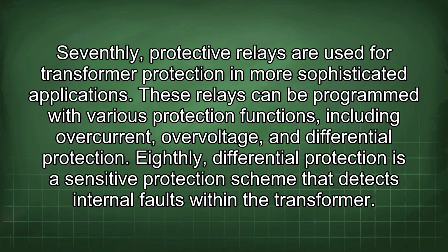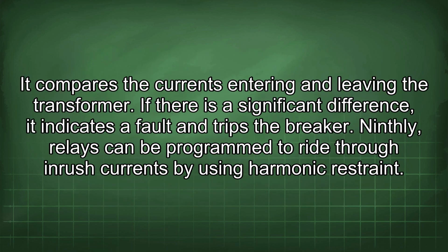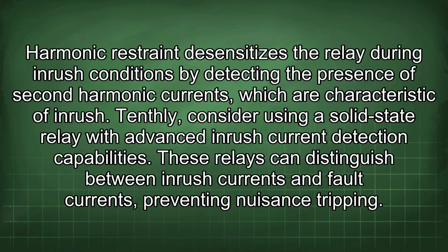Seventhly, protective relays are used for transformer protection in more sophisticated applications. These relays can be programmed with various protection functions, including overcurrent, overvoltage, and differential protection. Eighthly, differential protection is a sensitive protection scheme that detects internal faults within the transformer. It compares the currents entering and leaving the transformer. If there is a significant difference, it indicates a fault and trips the breaker. Ninthly, relays can be programmed to ride through inrush currents by using harmonic restraint. Harmonic restraint desensitizes the relay during inrush conditions by detecting the presence of second harmonic currents, which are characteristic of inrush. Tenthly, consider using a solid-state relay with advanced inrush current detection capabilities. These relays can distinguish between inrush currents and fault currents, preventing nuisance tripping.